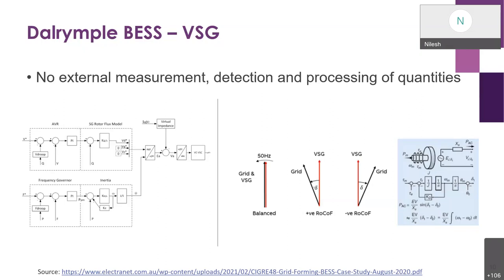The synthetic inertia provided by the battery is governed by the fundamental power transfer equation, that is, it is dependent on the voltage angle difference between two nodes. No external measurement processing and detection is required for most of the FFR, or fast frequency response, from this battery. The voltage phasor has its own rotational speed and frequency, not following the grid frequency but generated internally as an independent reference as part of the grid forming function. Based on the angle movement with the coupling point, the battery responds.